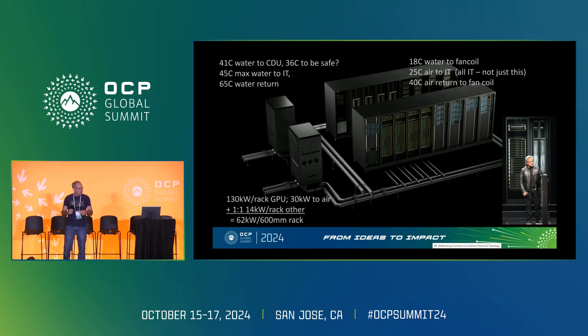There are parts of servers that, like carbon-based life forms, like it a little bit colder. So some percentage will probably use traditional data center cooling — whether that's a fan wall, an overhead unit, or a delta cube. The technologies exist. Some people with ASHRAE A3 and A4 can run it hotter, but the hotter you make the cold aisle, the hotter you make the hot aisle, and fan coils don't necessarily like to work at 60°C. So there's a mix going on right now.